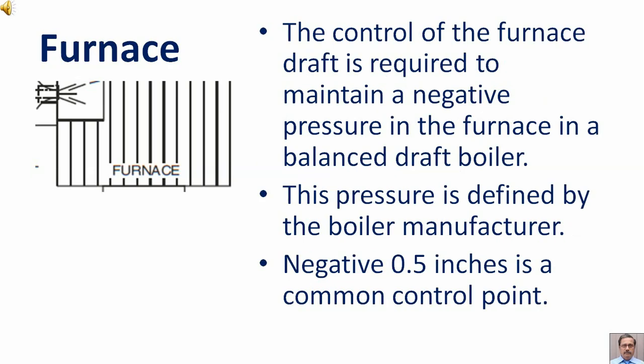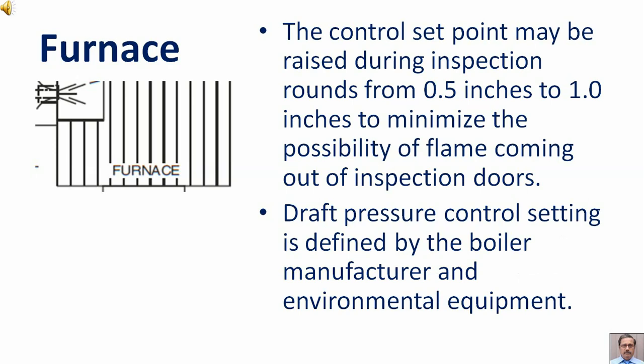The control of the furnace draft is required to maintain a negative pressure in the furnace in a balanced draft boiler. This pressure is defined by the boiler manufacturer; negative 0.5 inches is a common control point. The control set point may be raised during inspection rounds from 0.5 inches to 1 inch to minimize the possibility of flame coming out of the inspection doors. Draft pressure control setting is defined by the boiler manufacturer and environmental equipment.